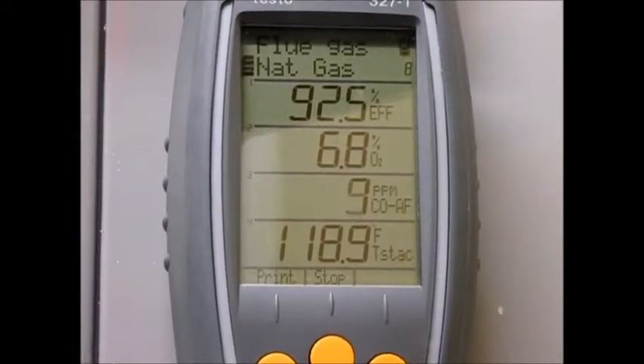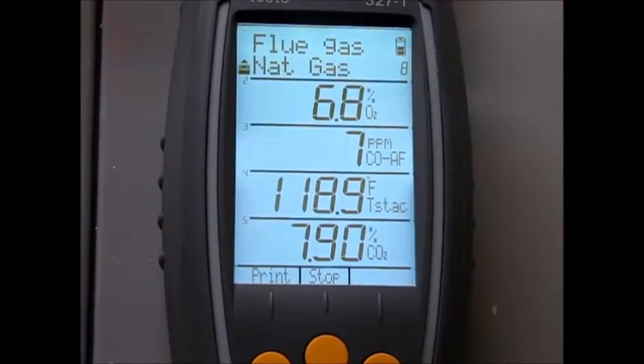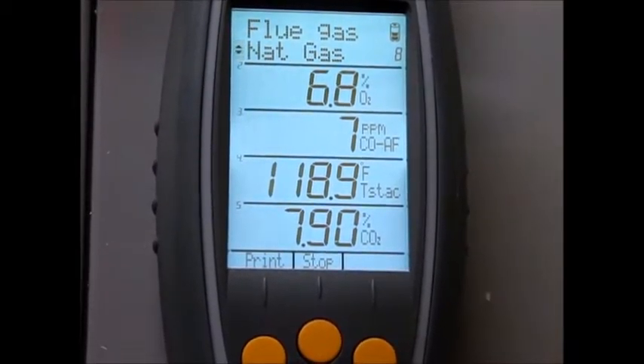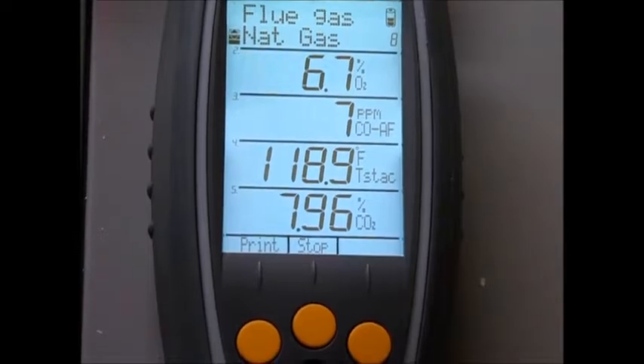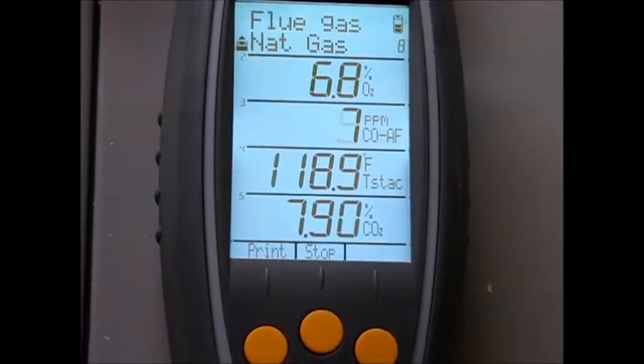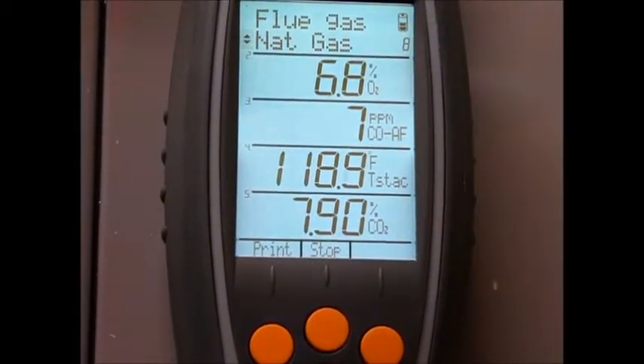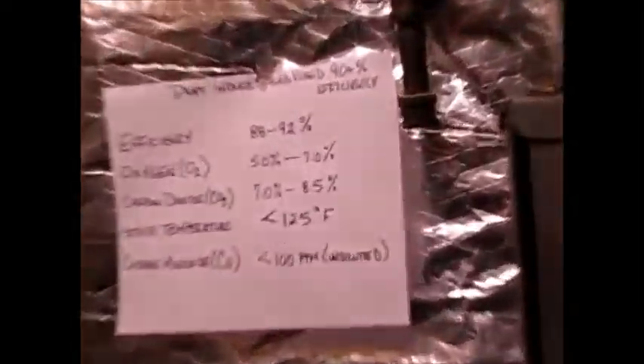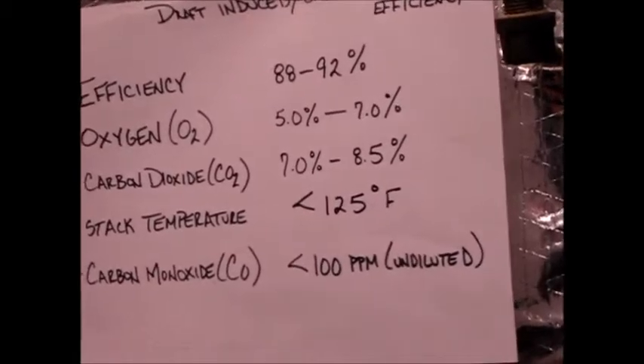Stack temp, 118, 119 degrees, which on a 90% furnace in the stack, we want to be less than 125 degrees. Carbon dioxide, we're hovering around 7.9%, which our optimal ratings are anywhere between 7 to 8.5% on this furnace.